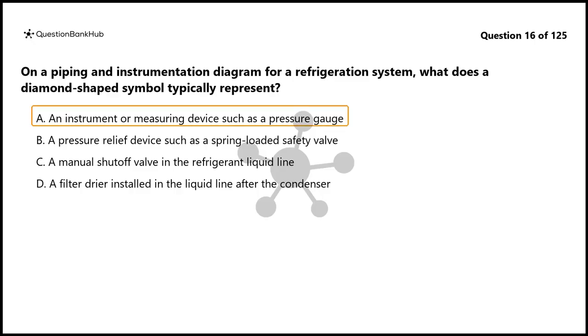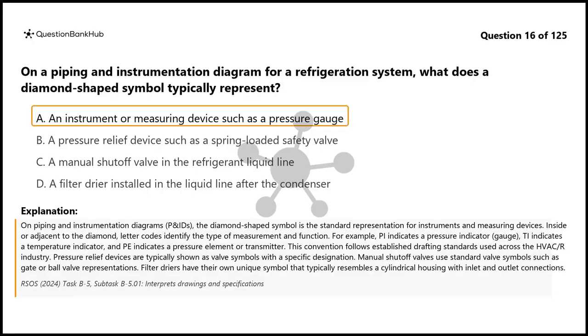The correct answer is A. On piping and instrumentation diagrams, P and IDs, the diamond-shaped symbol is the standard representation for instruments and measuring devices. Inside or adjacent to the diamond, letter codes identify the type of measurement and function. For example, PI indicates a pressure indicator, gauge, TI indicates a temperature indicator, and PE indicates a pressure element or transmitter. This convention follows established drafting standards used across the HVAC/R industry.